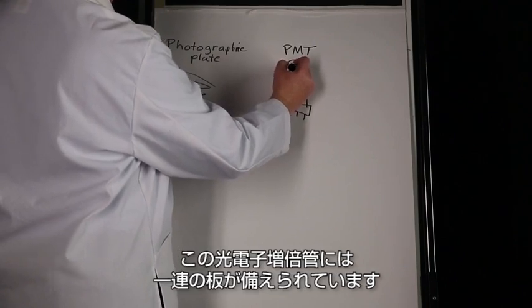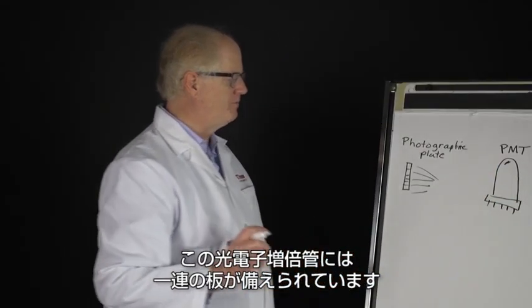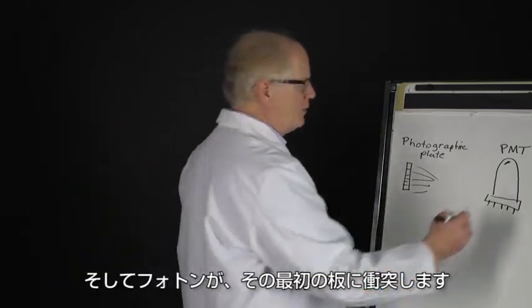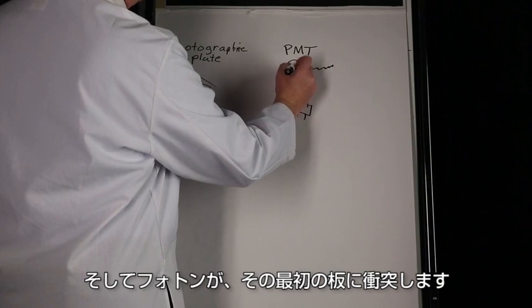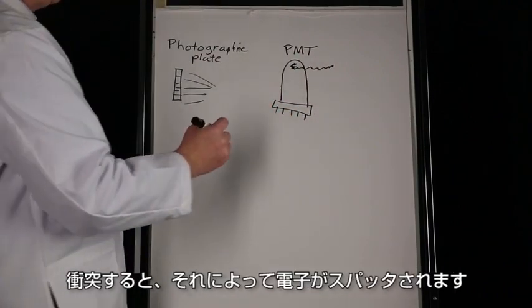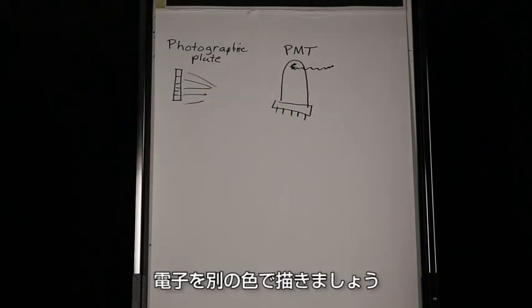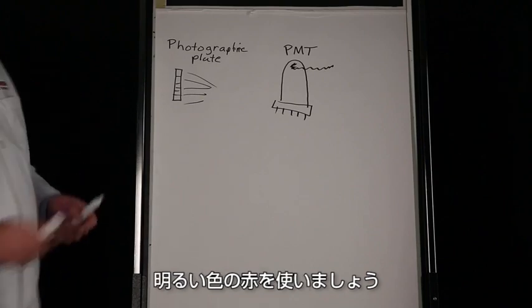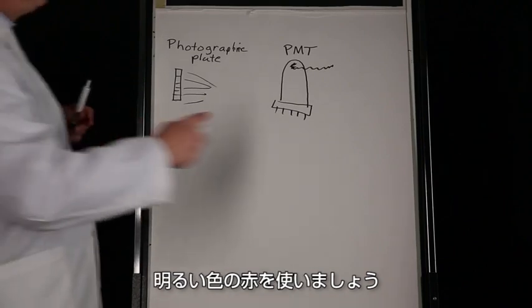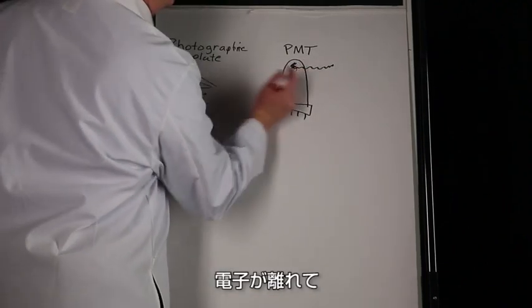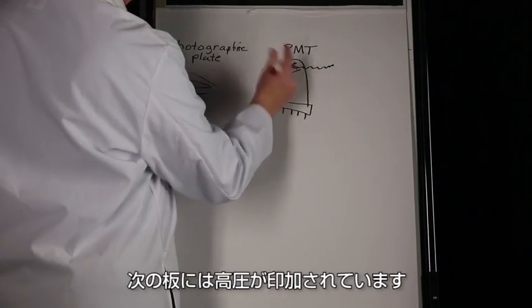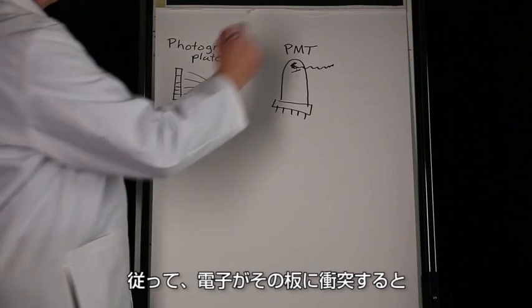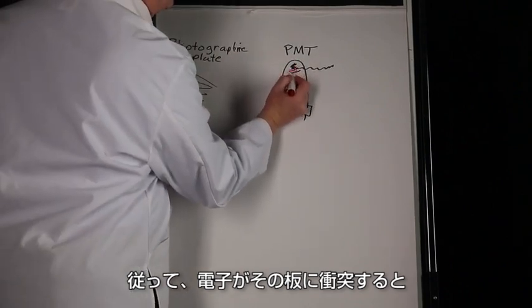That photo multiplier tube has in it a series of plates, and the photon would come in and strike that first plate. When it did, it would cause an electron to sputter. The electron would come off and move down and hit the next plate. That next plate was at a higher voltage, so when that electron struck that plate, I would end up with a bunch of electrons coming off.